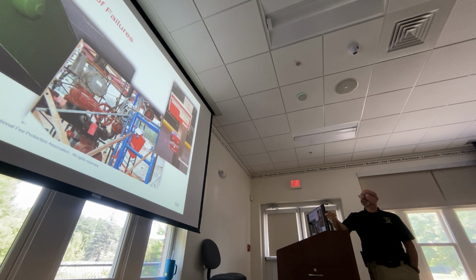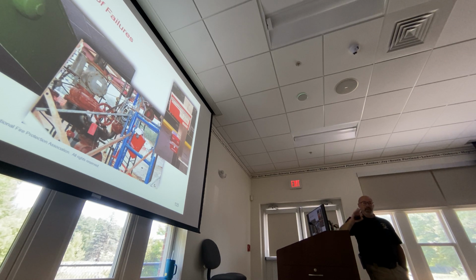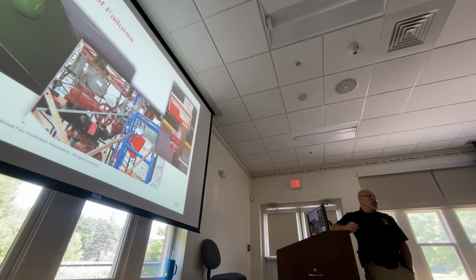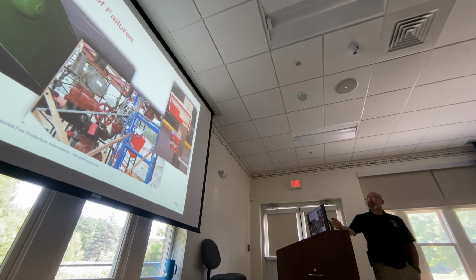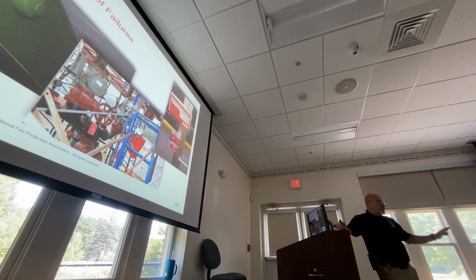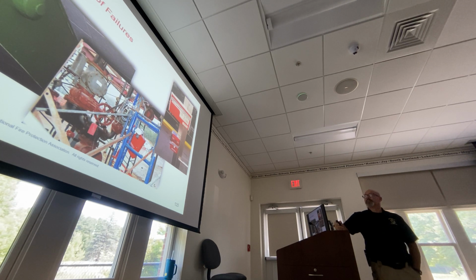How about this? This says not in service. Don't look at the mounting of it, that's a different story. You could have building maintenance issues, like water leaks or structural decay that has impeded the system. So should that not have a lockout tagout? Well, lockout tagout would be back at the electrical panel, where you'd lock out the main breaker. But if you see this, does that mean the system's not in service? No.